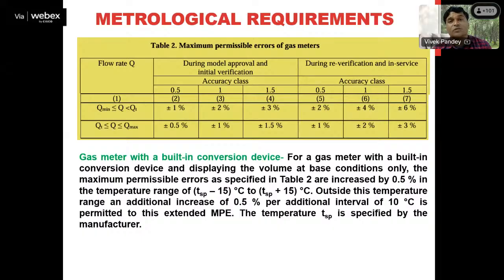The tolerance level is as you can see: if a gas meter is of accuracy class 0.5, then during model approval its maximum permissible error can be plus minus 1% when the gas meter is tested between minimum flow rate and transitional flow rate. And the same gas meter of accuracy class 0.5, if tested from transitional flow rate to maximum flow rate, has a maximum permissible error of plus minus 0.5%. So you can see what I was trying to explain: the transitional flow rate is a point where the MPE changes, the accuracy of the instrument changes, fine.